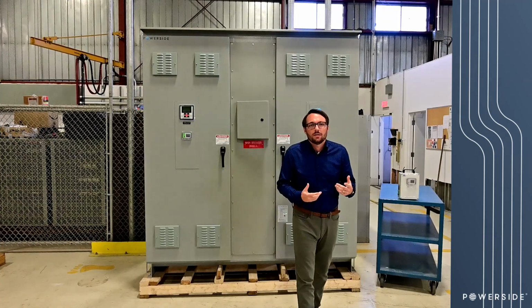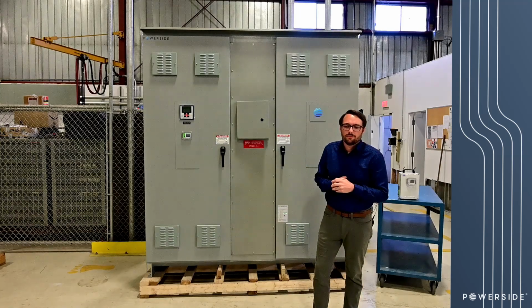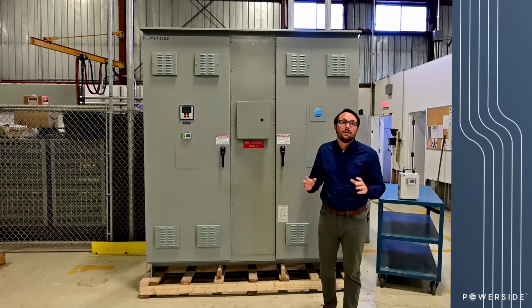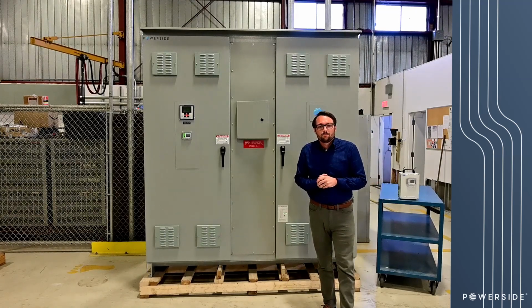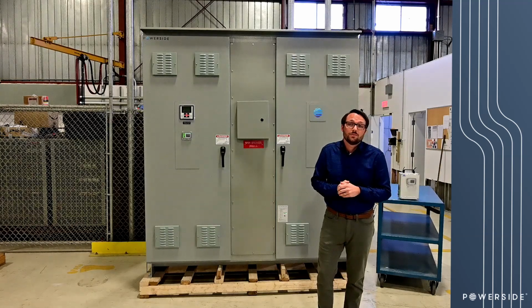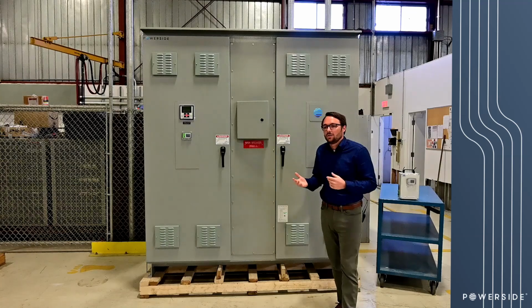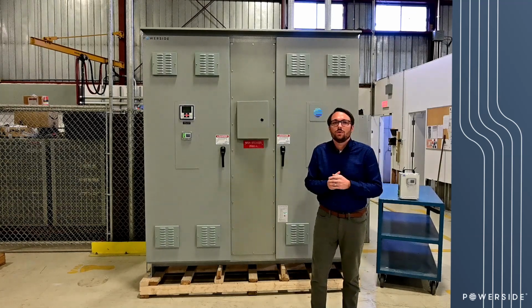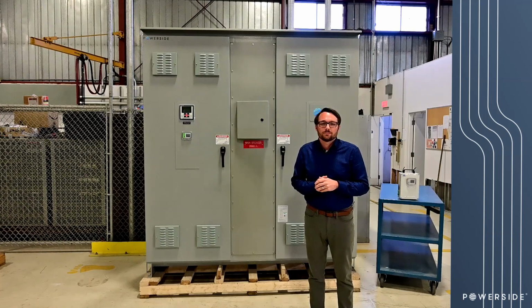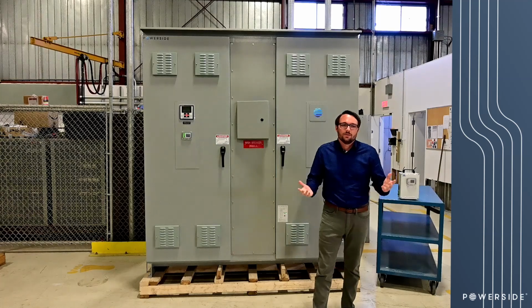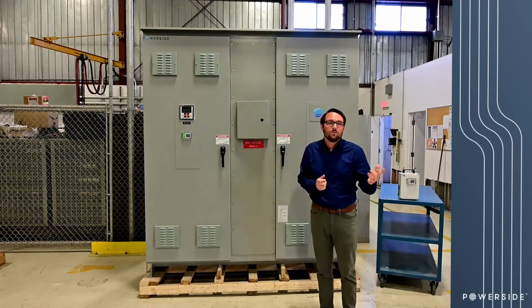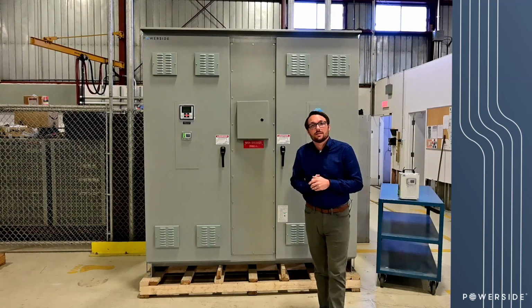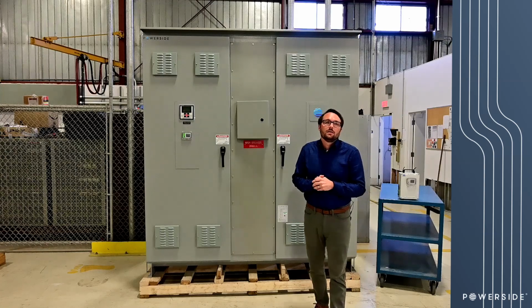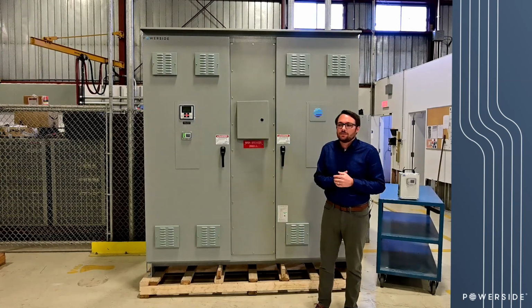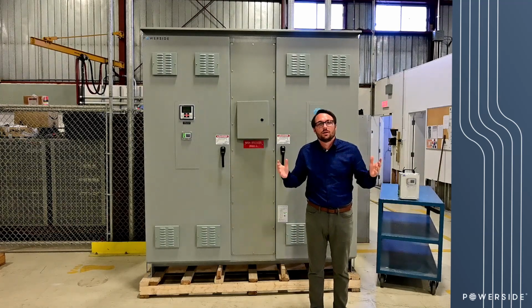But when we got a little bit deeper and peeled the layers back of the onion, we began to figure out that they already had power factor correction equipment scattered throughout the entire facility. However, no one was sure if it was operating, if it had failed, if there was any maintenance done, etc. So we offered to do a site visit, meet with the customer, and we looked at some of the units on site. These units were from all different types of manufacturers, some older, some newer, but all of them had essentially failed in some way, either with blown fuses, capacitor cells that were bulged, or contactors that had also failed or burnt up.